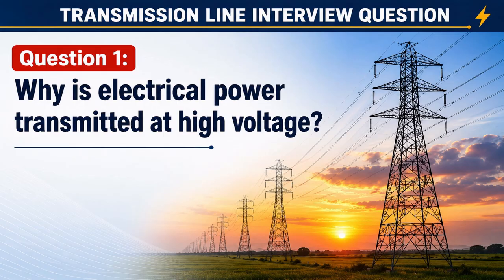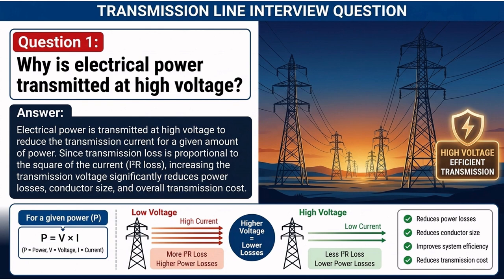Why is electrical power transmitted at high voltage? Electrical power is transmitted at high voltage to reduce the transmission current for a given amount of power. Since transmission loss is proportional to the square of the current, I squared R loss, increasing the transmission voltage significantly reduces power losses, conductor size, and overall transmission cost.